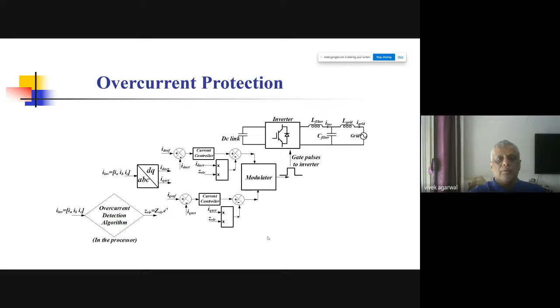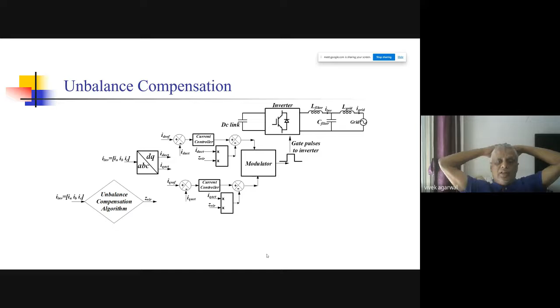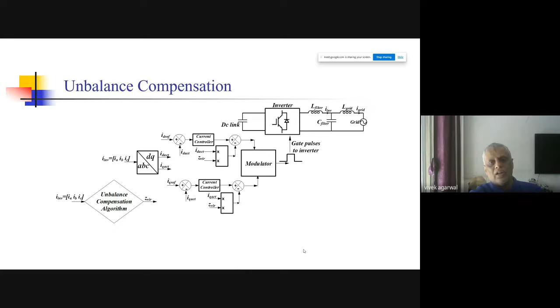Another case: your inverter may be feeding predominantly positive sequence voltages into the system and be low on negative sequence voltages, causing an imbalance in voltages across the grid. You can design the virtual impedance, ZVIR, so that the inverter output is predominantly negative or positive sequence in such a way that their mix leads to a balanced voltage applied to the grid. So any imbalance being created can be corrected.